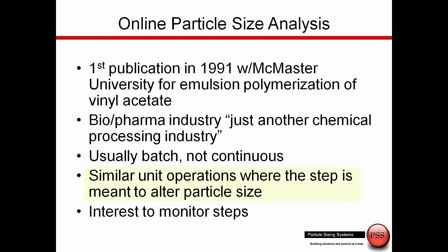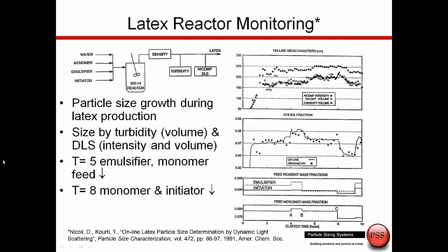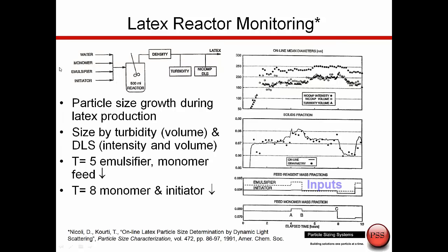Here's information on this first online system, installed in 1991. In this setup we have a reactor with water, monomer, emulsifier, and initiator coming in. Downstream of the reactor we're taking several measurements: a density or gravimetric measurement to understand concentration, and then both turbidity and the online NICOMP DLS system to look at particle size. These are the different inputs, and plotted as a function of time in hours, as they altered these inputs they were looking for the change in concentration and particle size.